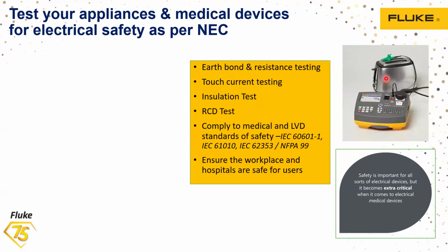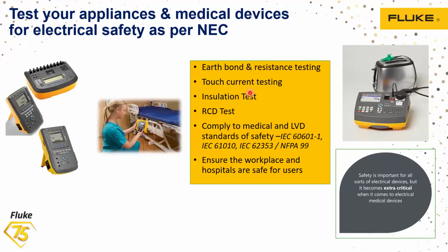Some of the appliances will have the body as the earthing, right? So how much bond is available, and how much touch current is tested? How much protection is available on the touch current? Then the insulation test, and also whether an RCD is available in the facility or in any special machine. For example, assume you have a special equipment installed, and inside that equipment there are RCDs, so you can ensure it is as per the standard.